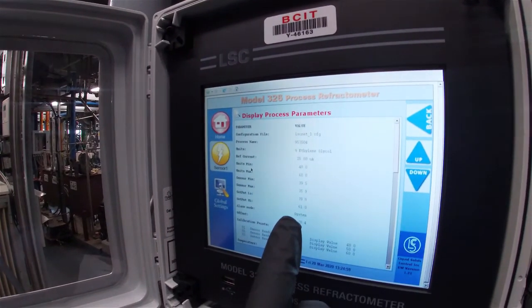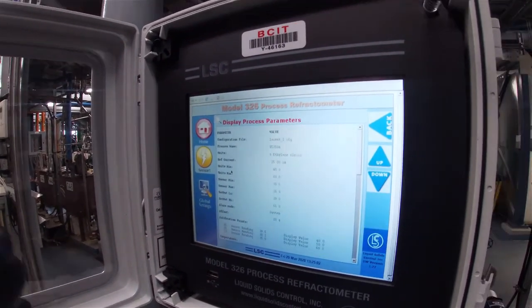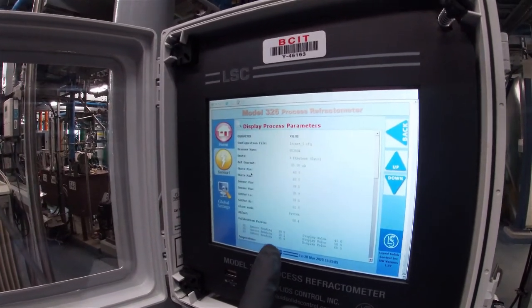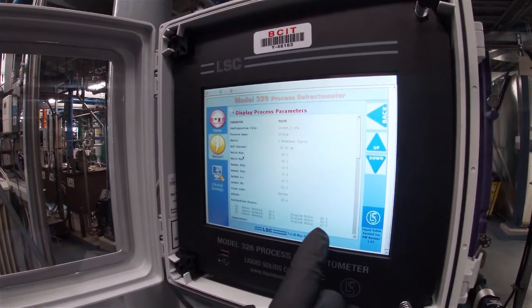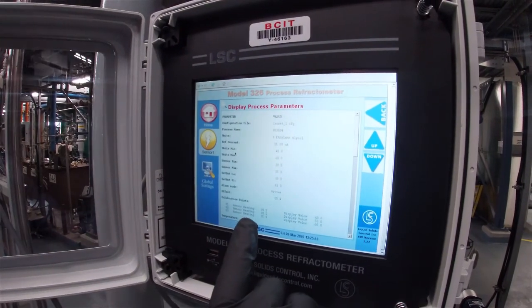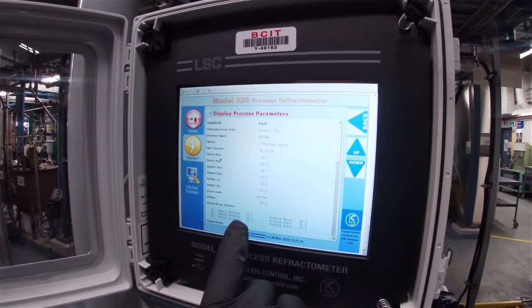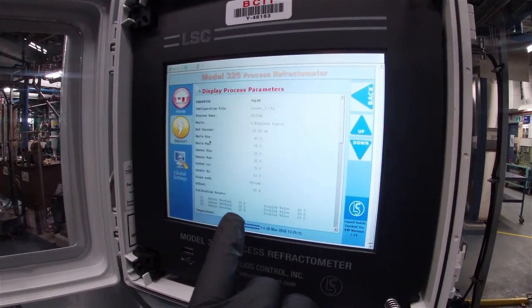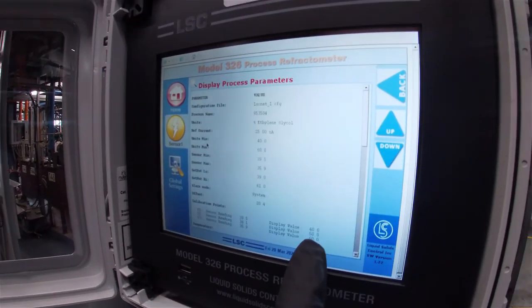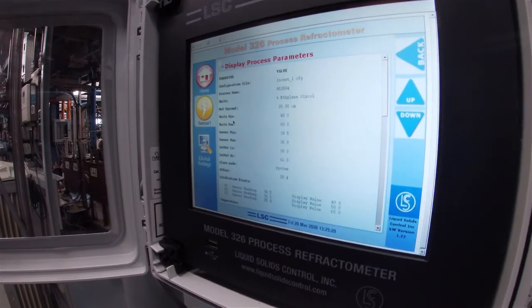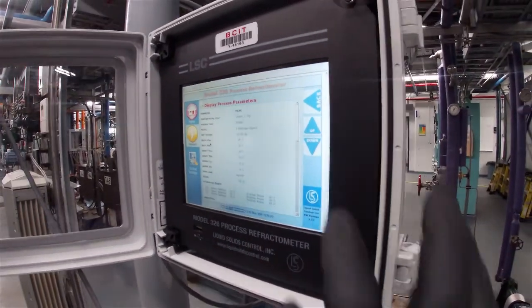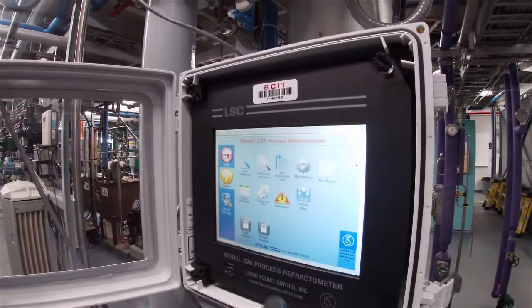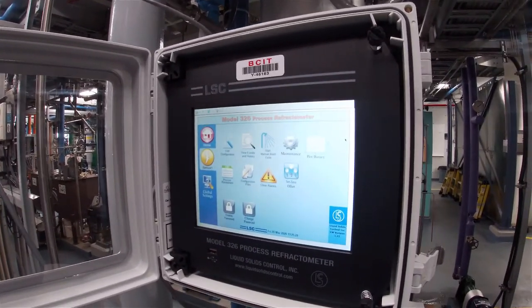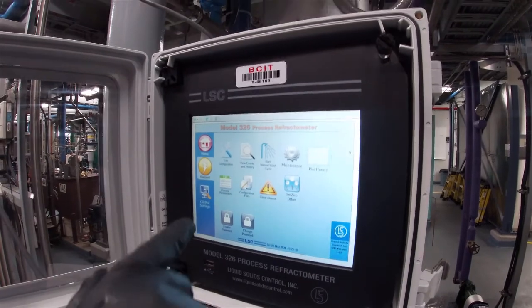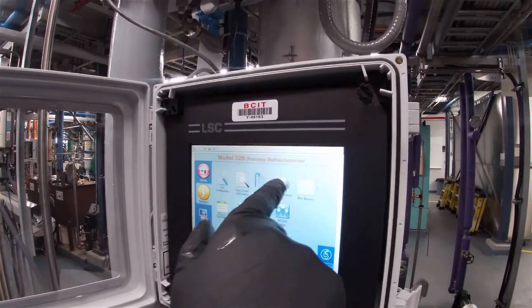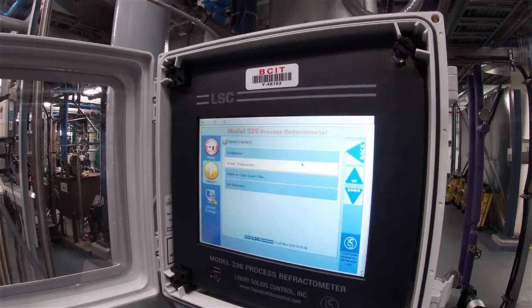Set point high is running at 60 and 39, so that's a little bit over range. The sensor itself shows what readings it's going to be at. This is the actual microamps coming back, so 39.5 microamps is a value of 40%, 38.1 is a value of 50%, and 35.9 is a value of 60%. So we're going to get out of this display and go into calibration. Where's calibration? Under maintenance. So maintenance for calibration.